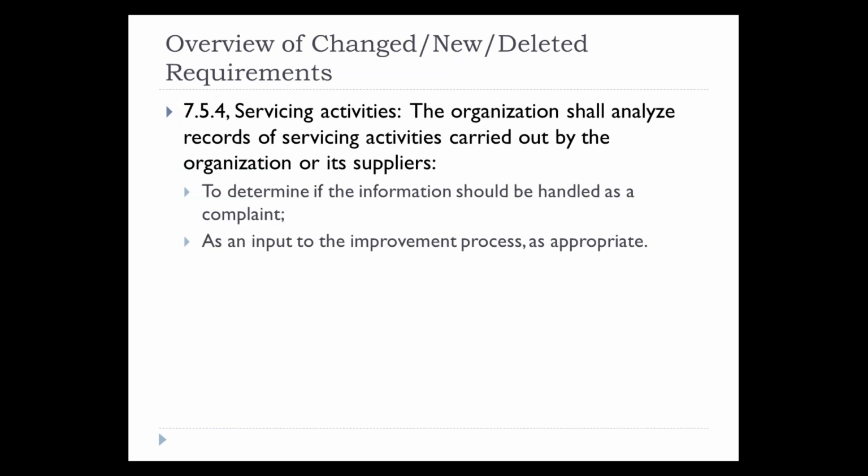Servicing activities. The organization shall analyze records of servicing activities carried out by the organization or its suppliers to determine if the information gained from the service call should be handled as a complaint and as an input to the improvement process. So if the organization is doing servicing as part of its service and it's learning about issues in the field, these have to flow back to the organization. The organization needs to make a determination whether it needs to be handled as a complaint or not. And all this information needs to serve as an input to the improvement process.